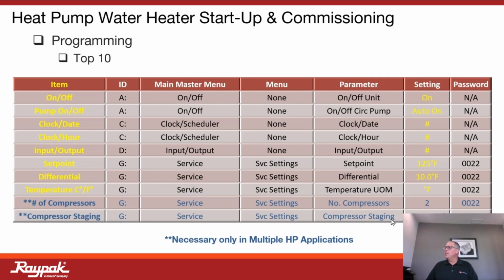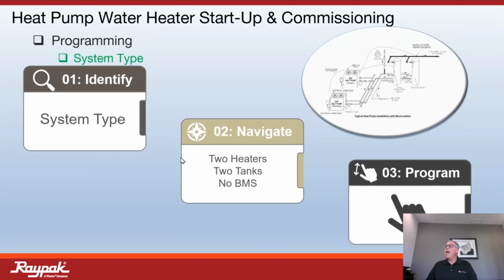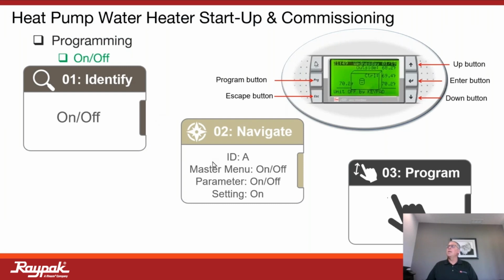Compressor staging. This is interesting. We're going to talk about that and show you more what that means, but the default is simultaneous, and we can program over to a staggered method. So we'll talk about this more fully here. So again, just navigating, knowing what your system looks like is the biggest thing. What is my number of units? Do I have 2 tanks that are properly reverse returned? Do I have 4 tanks properly reverse returned? All these individual things again.